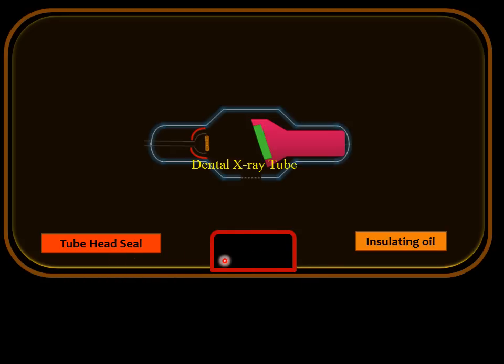Now we've said that two types of energies are produced: the long wavelength low energy and the short wavelength high energy. The long wavelength low energy x-rays are absorbed in the patient and are harmful for the patient, so we have to filter this.